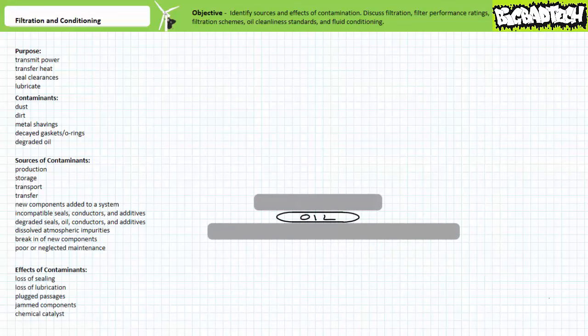Regardless of the source, contamination control is essential, since parts like the piston inside the barrel of a cylinder or the spool inside a directional control valve are machined such that a tiny tolerance exists between them. A thin film of oil lubricates the moving parts and seals the separate passages. Small particulate contaminants under high pressure may abrade surfaces over time and progressively decrease the sealing ability afforded by the thin film of oil. Large contaminants may accumulate and slow or even jam a moving component in place. Add to this difficulty, large contaminants may break apart into smaller particles, further damaging the system. Additionally, contaminants can plug sensing or pilot orifices and act as an oxidizing catalyst, contributing to undesirable chemical changes.